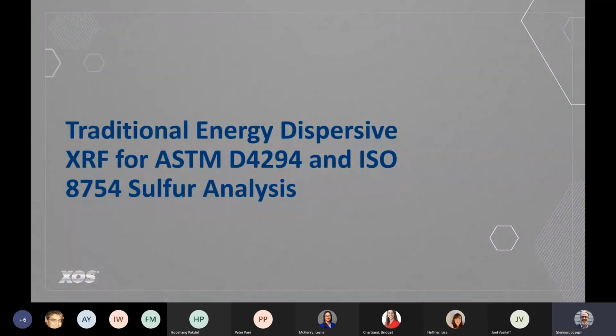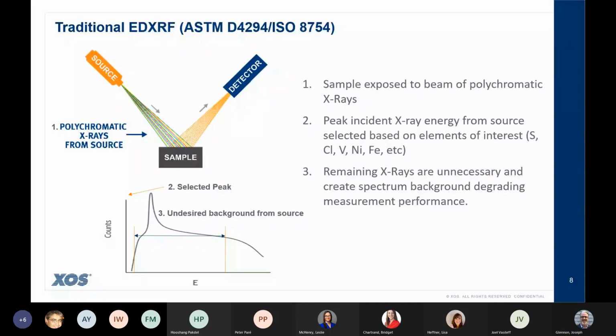So I just want to give you, we'll compare what we'll call traditional EDXRF versus advanced HDXRF, which is what XOS does. So when we say traditional, it's sort of referring to what our competition has out in the field. So I'll give you an idea of how traditional EDXRF works. You can see in the diagram that an X-ray source exposes a beam of polychromatic X-rays straight to the sample. Peak incident X-ray energy from the source is selected based on the element of interest. All other X-rays are unnecessary and they create spectrum background, which of course degrades measurement performance.